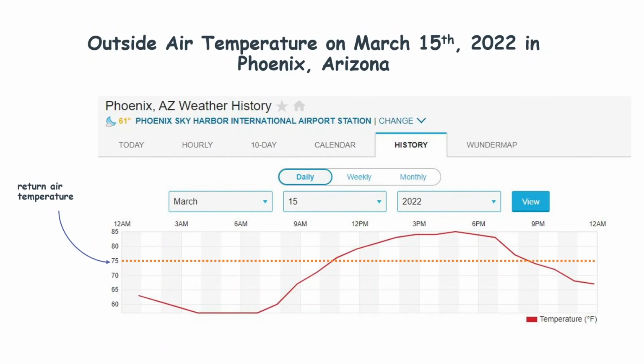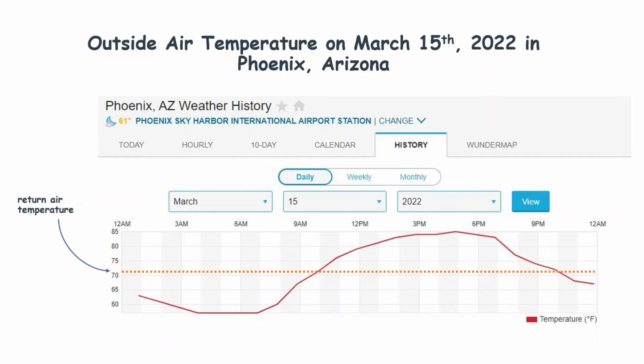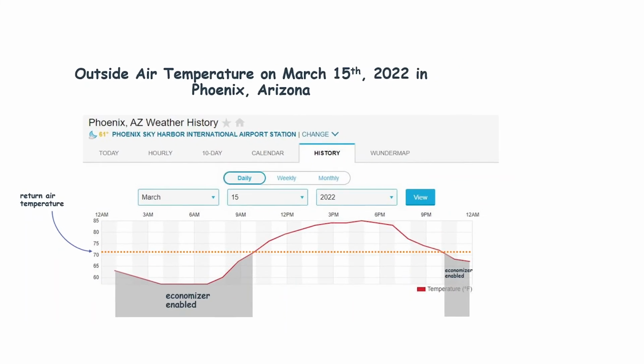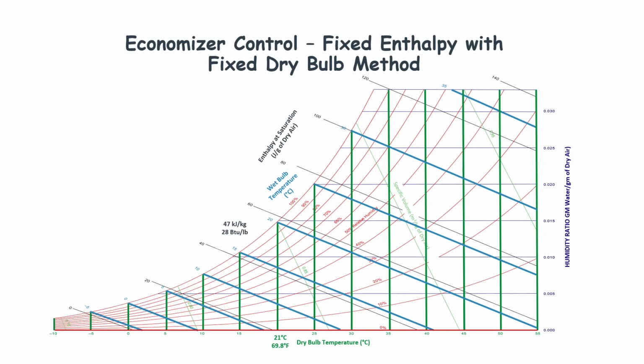But what if the indoor set point changes to 70 degrees Fahrenheit? This is when we can see the advantage of the differential dry bulb temperature method over the fixed dry bulb temperature method. With the differential temperature method, the economizer gets activated when outdoor air is below the return air, which is at 71 degrees Fahrenheit. But with the fixed dry bulb method, there are times that the economizer brings in outside air that is at a temperature above the return air temperature, which means that we are increasing the cooling load instead of decreasing it.